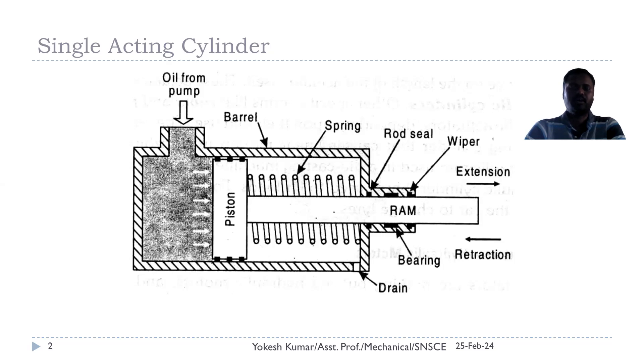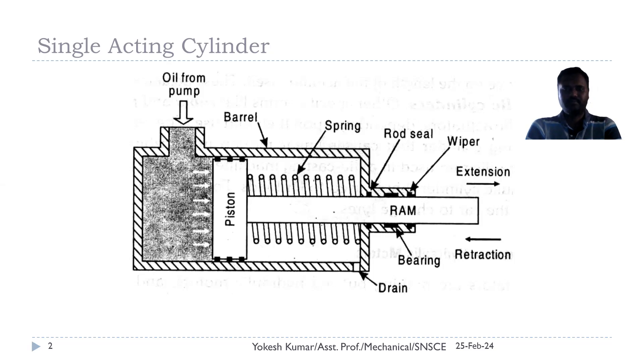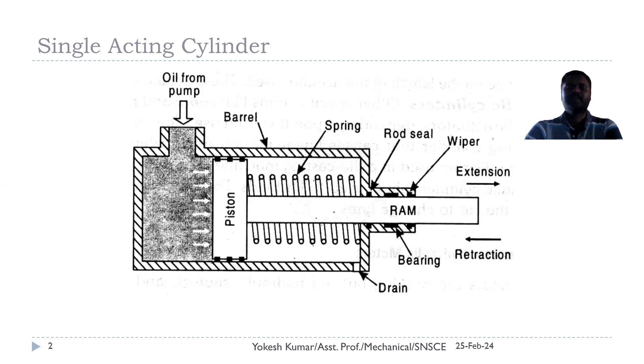Wiper seals are located on the outside of the cylinder. They are used to protect the ram from contamination by foreign contaminants like dust and rust, because the outer side of the ram is exposed to the ambient environment. Since the cylinder is operated to very close dimensional tolerances, hard contaminants entering the cylinder can damage internal parts. To overcome this problem, the cylinder is provided with a wiper seal.